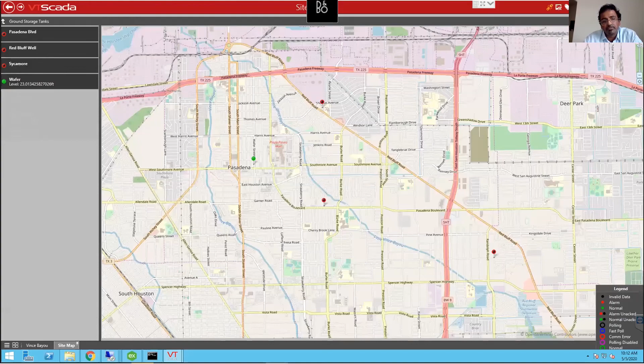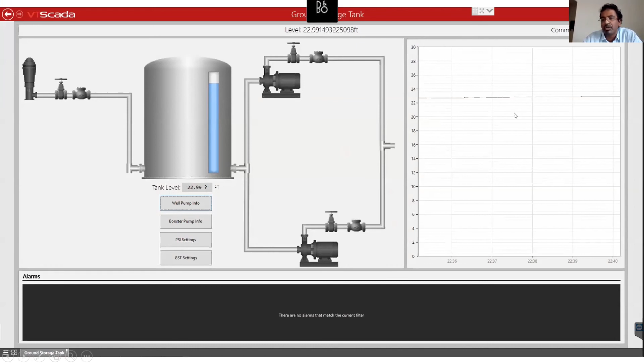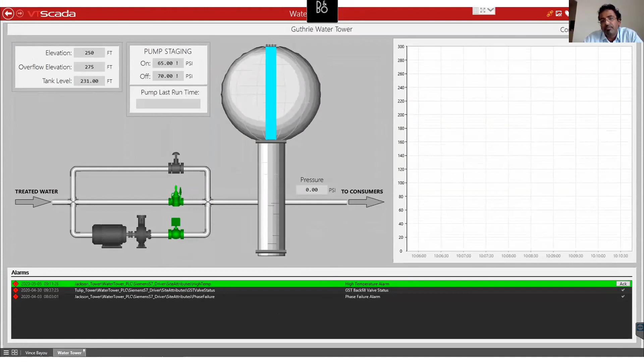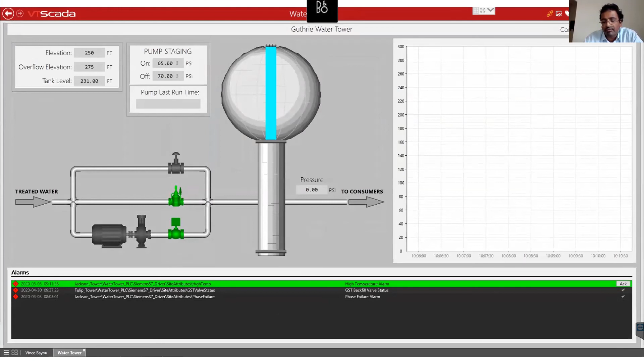As you can see from the level trend, we're polling the site on a faster basis right now, and you can see the gaps indicative of communication loss. This is a typical setup for a water tower. For both the water tower sites and the ground storage tank sites, we mainly do monitoring, and there isn't a lot of control presently there.